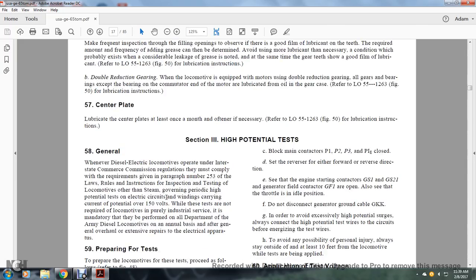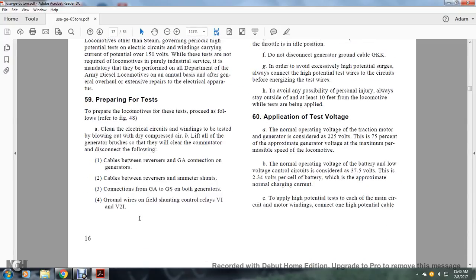Section 3, High Potential Test. General. Whenever the diesel-electric locomotive is operated under Interstate Commerce Commission regulations, the requirements of paragraph 253 of the laws and rules on inspection and testing of locomotives must be complied with. A high potential test is required for electrical circuits carrying current at potential over 150 volts. This test is mandatory for the Department of the Army for diesel locomotives on an annual basis, and after general overhaul or extensive repairs to the electrical apparatus.